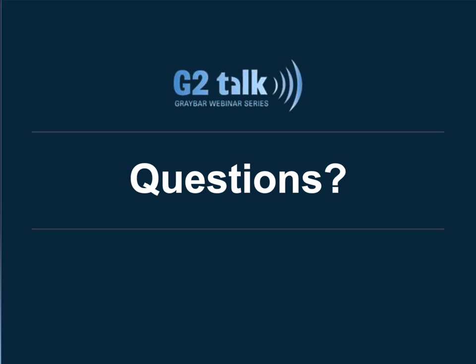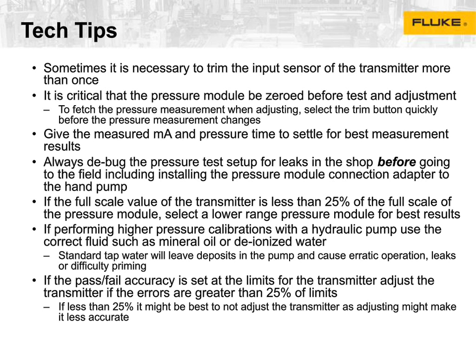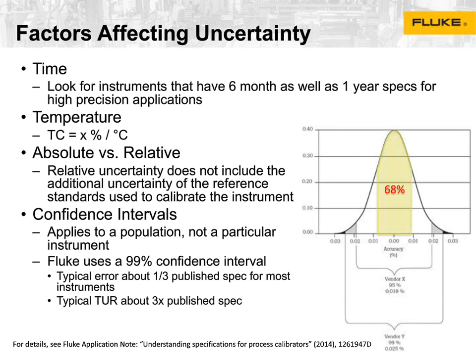Sure. So basically, the temperature coefficient is set by the manufacturer, and I'm actually going to go back to that slide if that's okay. Let's go backwards. Oops, wrong slide. There we are. Perfect. Okay. And so basically, I've got it set as the function here for TC is equal to X% divided by degree C. And basically what it's saying is that most manufacturers will put their gauges within a certain range, and then as you go out, you have to compensate. And they'll give you a number. X will be a value, 0.0012%, for example. And so for every degree C you fall outside of the temperature compensated range, you have to add an error factor. And so this can get pretty complex.